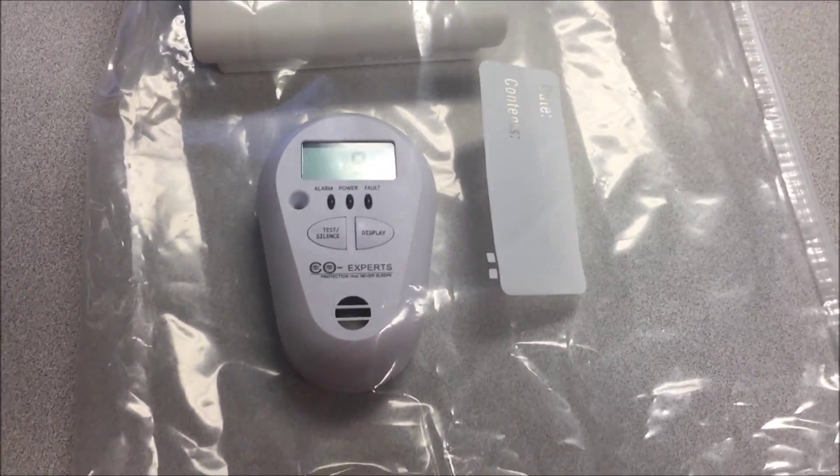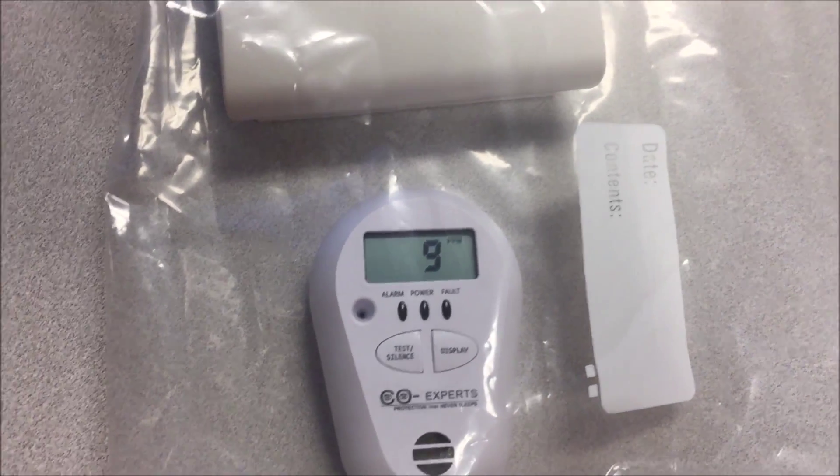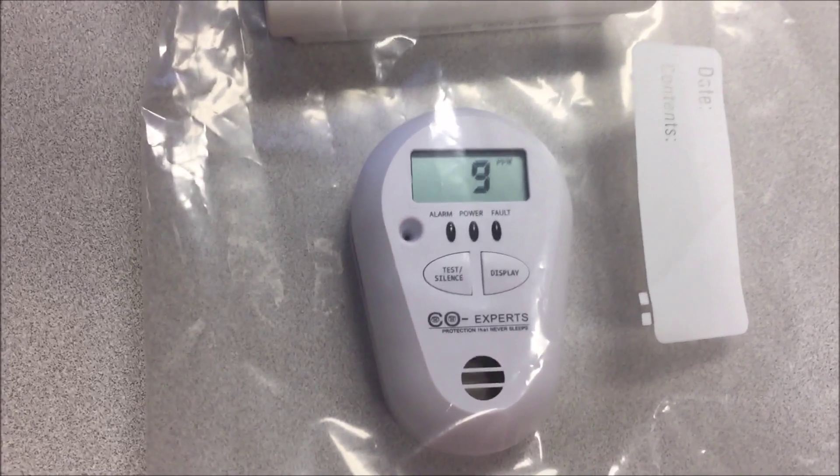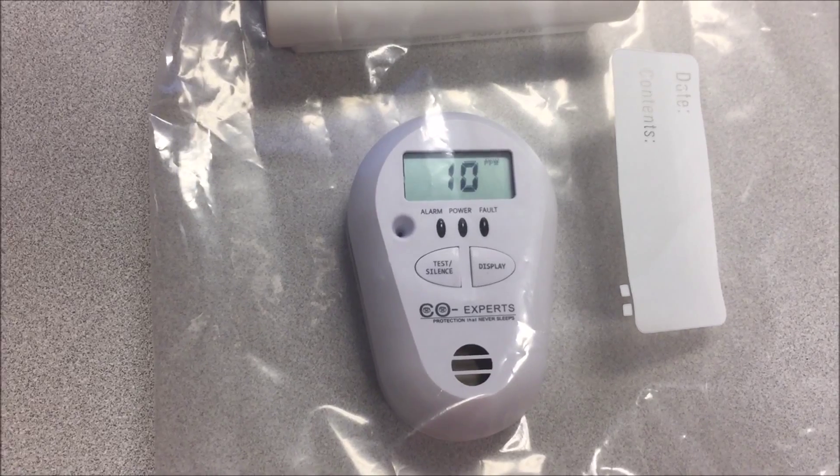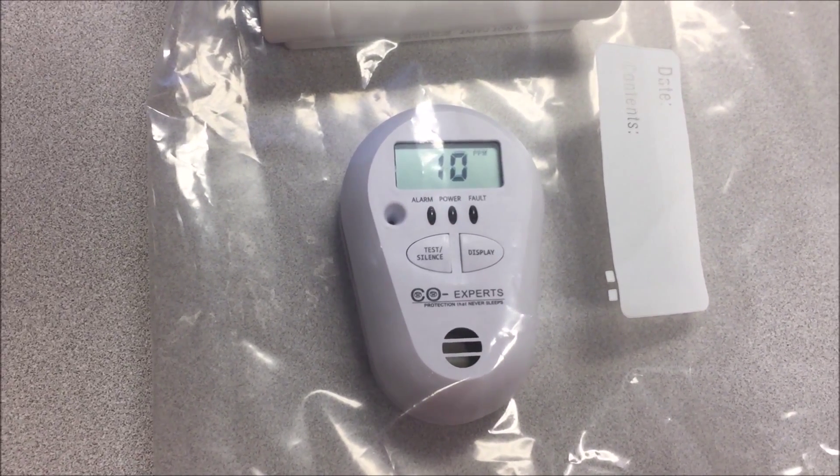The CO Experts monitor reads nine parts per million. If it gets to ten, we should get an audible alarm. There's ten parts per million — we'll give it a minute or so — and there's the alarm.